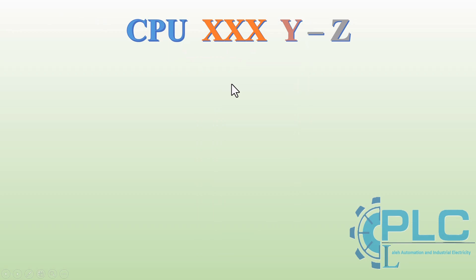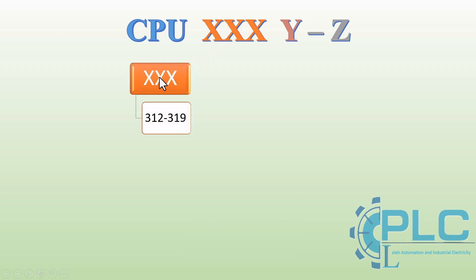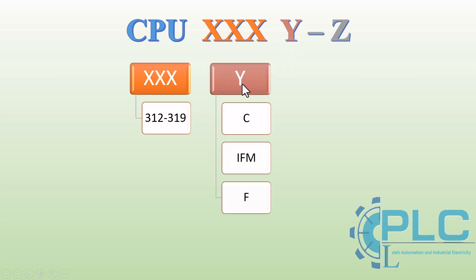Siemens S7300 CPUs follow a fixed naming pattern: CPU XXX Y-Z, where each part of the code provides important information about the CPU's capabilities. The three-digit number (X) refers to the CPU model, ranging from 312 to 319. Higher numbers indicate faster scan cycles, larger memory, and higher input and output capacity. The letter Y represents the type of CPU: no suffix means modular; C means compact with integrated inputs and outputs; IFM means integrated function module, similar to compact but with high-speed counters for precise applications.